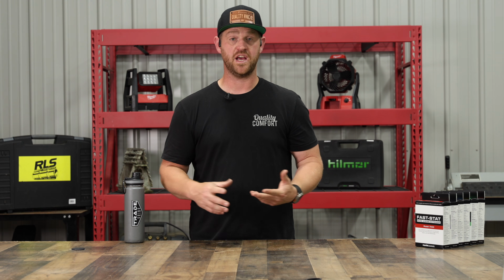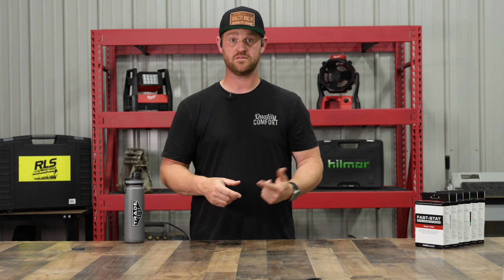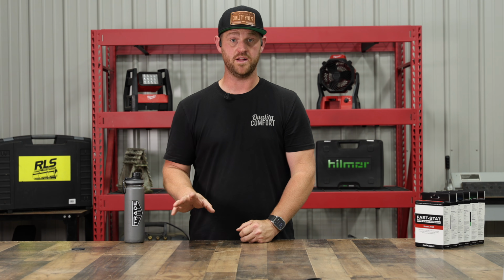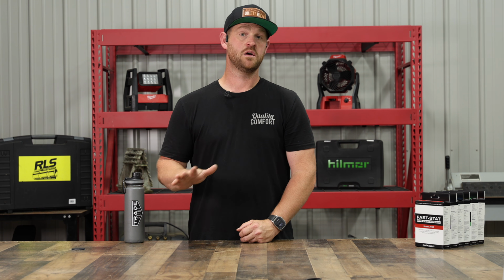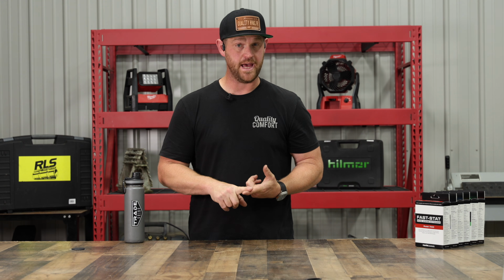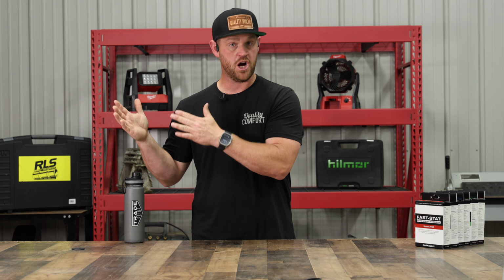So to boil it down quickly and easily, what is the difference between single stage, dual stage, and variable speed? Single stage is like a light switch: on, off, nothing in between. If it's a 2-ton unit, it's going to run at 2 tons whenever it runs, and then it shuts off. Two-stage equipment, depending on the manufacturer, typically runs first stage at around 60 to 70% of the unit's capability, and then second stage runs at 100% capacity. So you have a little bit of variance there, and it can adapt somewhat.